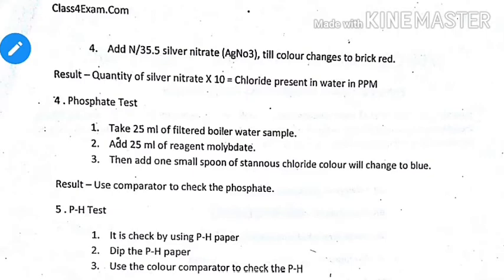A reserve of phosphate should be maintained in the boiler water to neutralize any hardness or scale formation. For the phosphate test: take 25 mL of filtered boiler water sample, add 25 mL of molybdate reagent, then add one small spoon of stannous chloride — the color will change to blue. Use a comparator to check the phosphate level.